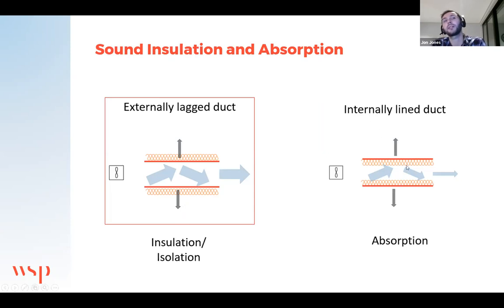Looking at the internally lined duct, which shouldn't be mixed up, actually this doesn't have much impact. Lining with an absorptive rock wool type product on the internal side of the duct doesn't have much impact in terms of the noise breakout from the duct. So if you had a noise sensitive location below, lining inside or not would likely result in a similar noise level at this location. But the benefit that this does provide is attenuation down the duct. As noise transfers down the duct, this absorption on the inside is going to slowly absorb the sound and reduce it as you propagate down from left to right, say.